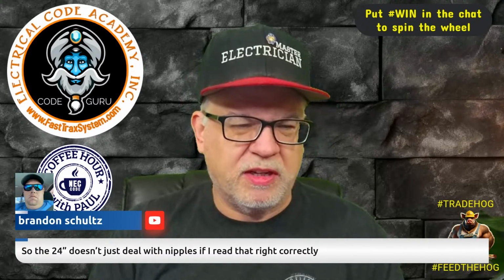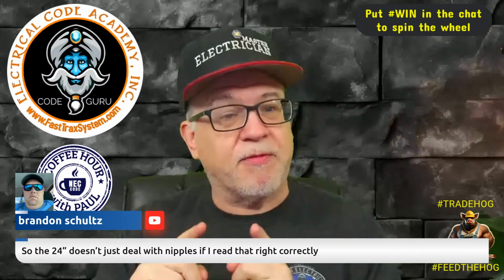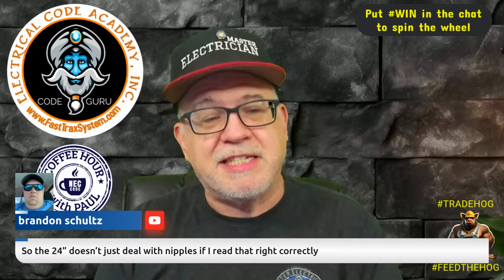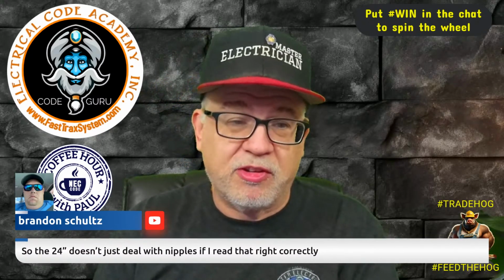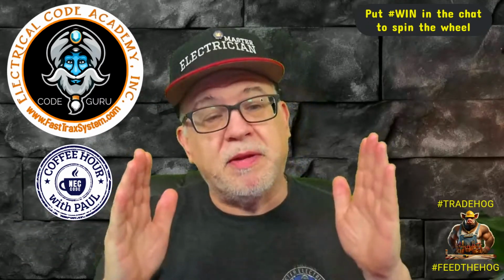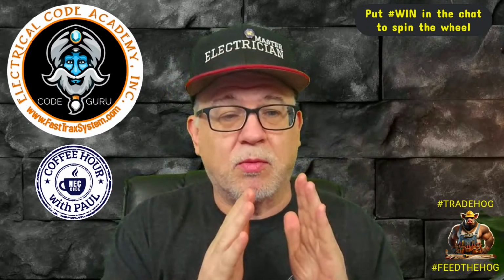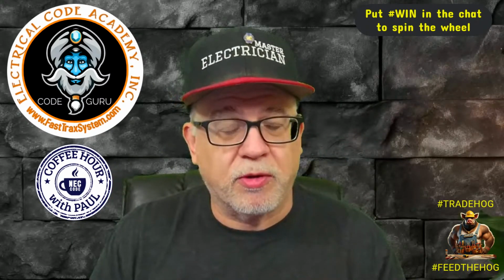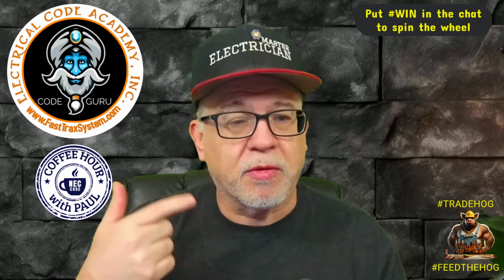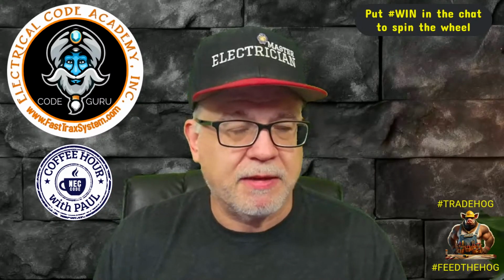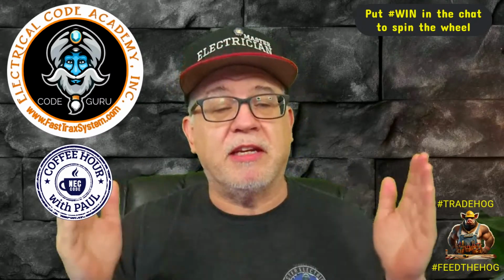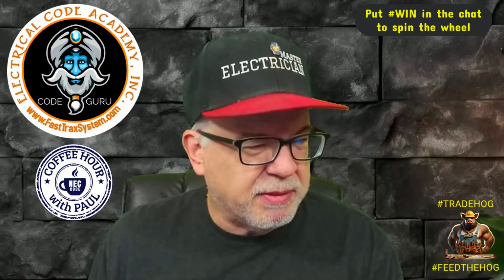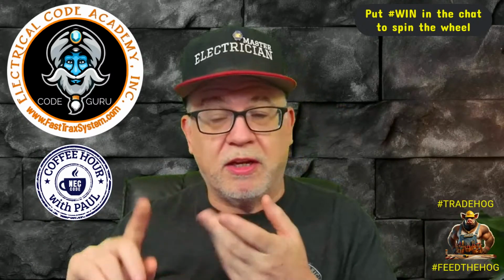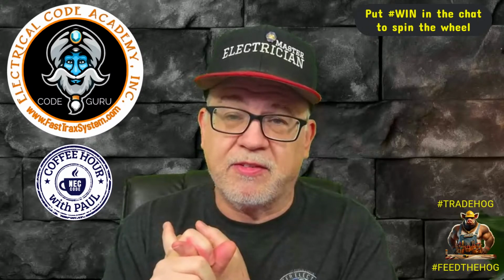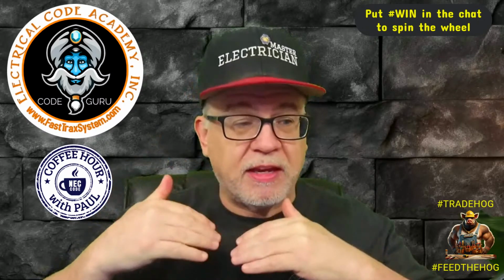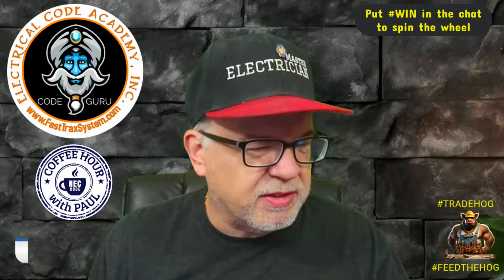Yep, so that's right. You have to go look at that code reference I gave you, because in the question it said it was an 18-inch. So again, you might still have the ambient you have to deal with. It explicitly tells you that you don't have to deal with it when it is less than 24 inches for the number of current carrying conductors in there. And the reason for that is it allows heat dissipation on each side. But it's important for you to read those rules and understand that there's more to 310.15(C)(1). There's other things in there that you have to be aware of.